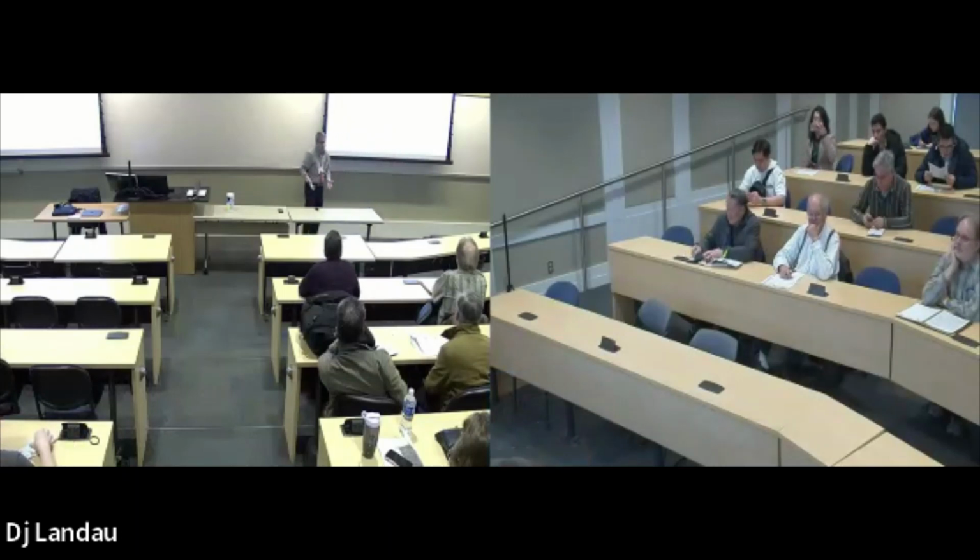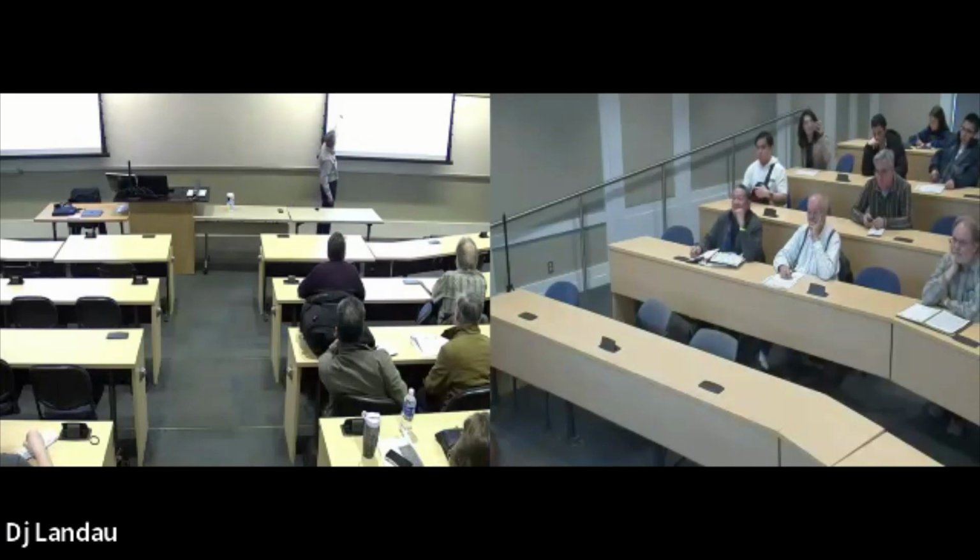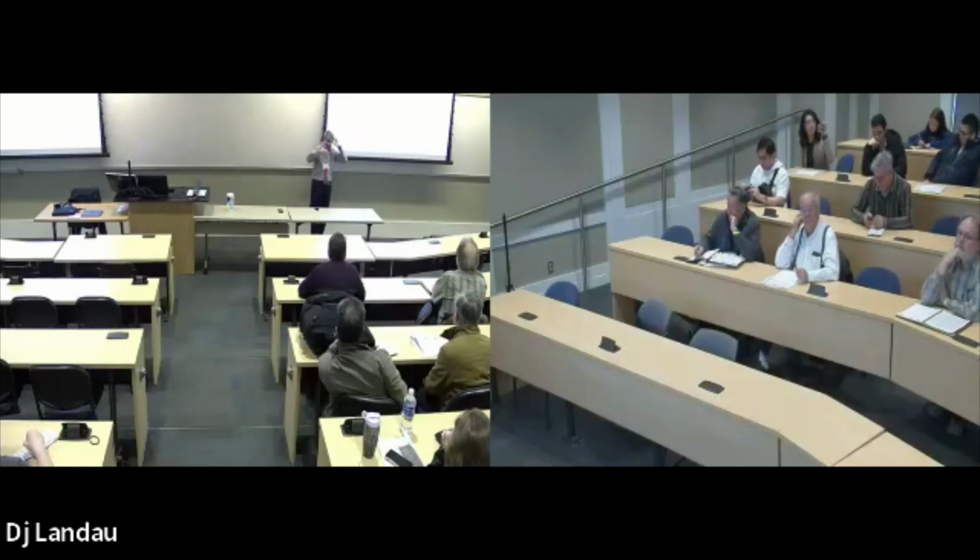But we don't have to do that now because we first of all generated a very high voltage and stepped it up even higher. So in Ed's power company here, he steps the voltage up at the substation through transformers anywhere from 138 to up to 765,000 volts. And when you step the voltage up that high, the current goes down.